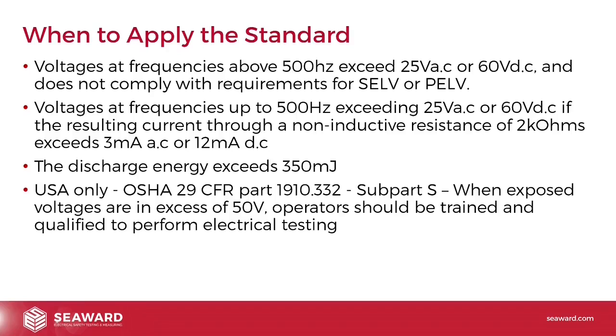So when do we apply the standards? Mainly we're going to be talking about EN 50191, that's for the UK and Europe. Voltages at frequencies above 500 Hz and exceeding 25 volts AC or 60 volts DC, and do not comply with the requirements for SELV or PELV.